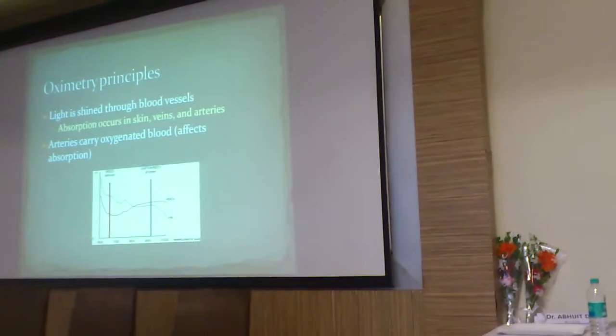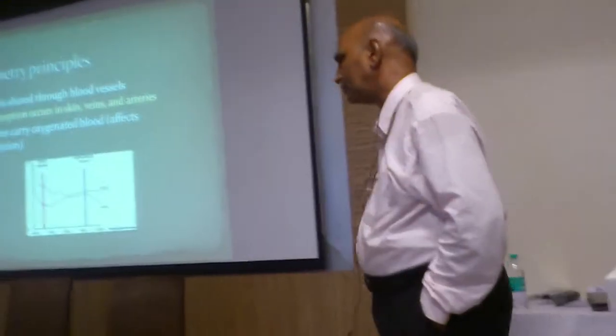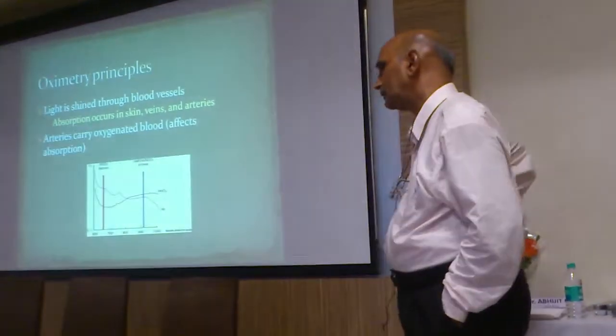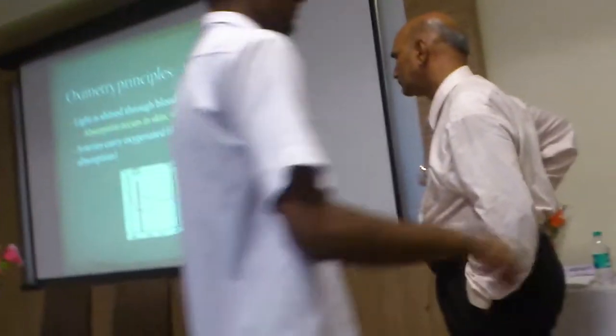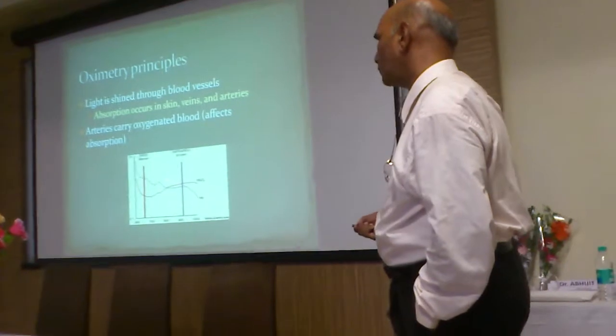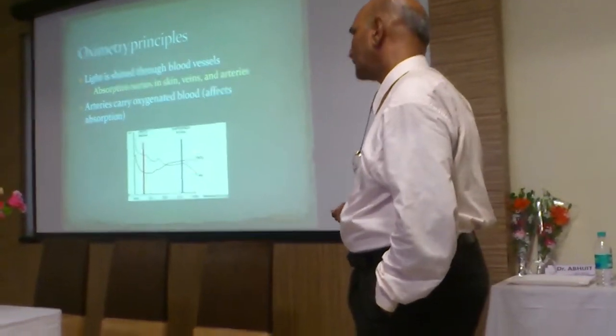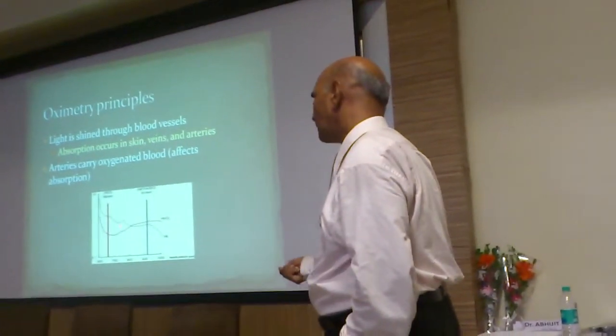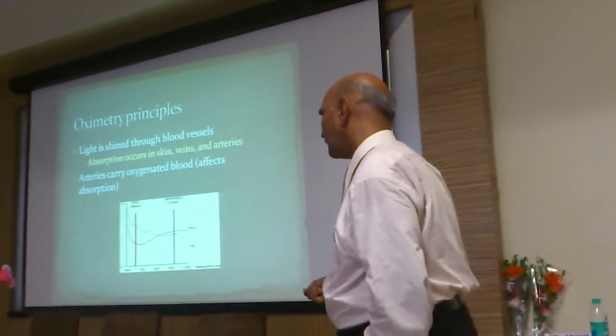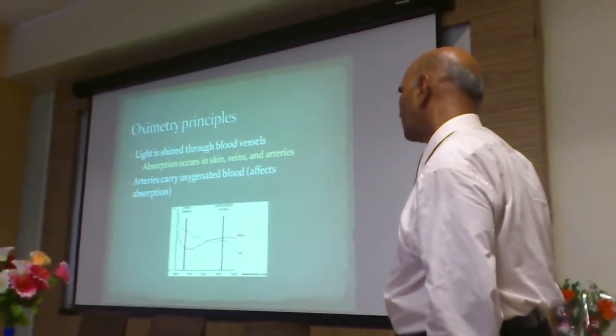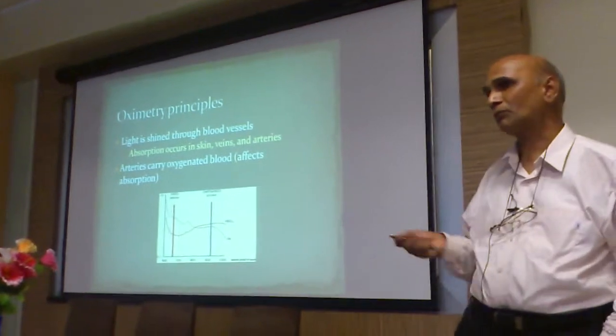What is the operating principle? Light is passed or shined through the blood vessels. The absorption occurs in skin, tissue and the arteries. The arteries carry oxygenated blood and affect the absorption. There are two curves — red at 660 nanometres and infrared at 910 nanometres. This is the electromagnetic spectrum. The absorption curve for HbO2 (oxyhemoglobin) and Hb (hemoglobin) are shown. We make use of these absorption properties of haemoglobin and oxyhaemoglobin to detect the concentration of oxygen inside the patient's blood. This technique is non-invasive — you don't have to prick or put anything inside the body. It looks at the fingertip, or the earlobe, or the forehead.